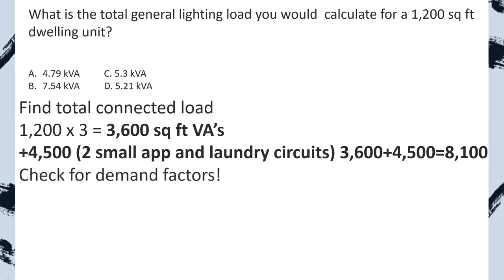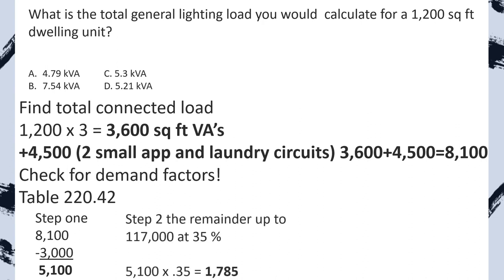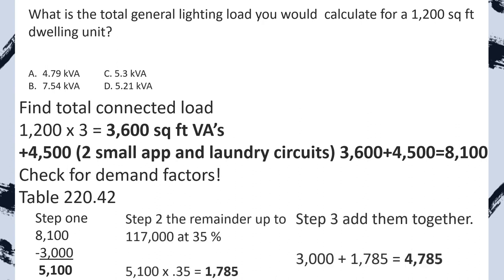Now we check for demand factors. We head to table 220.42, step one, we minus 3,000 and take it at 100%. Step two, we multiply that remainder by 0.35. All we have to do now is add them back together, and we end up with a new reduced load of 4,785 VAs, and we select A. Great job.